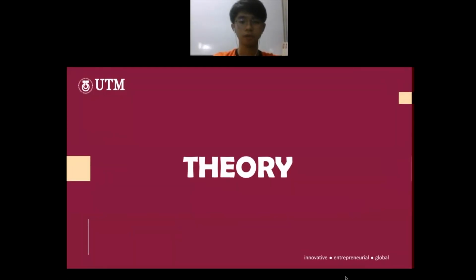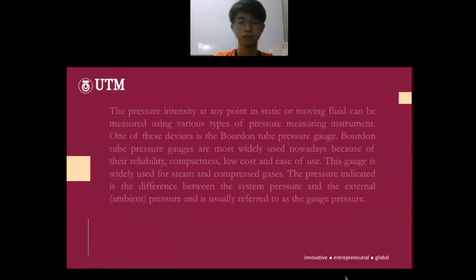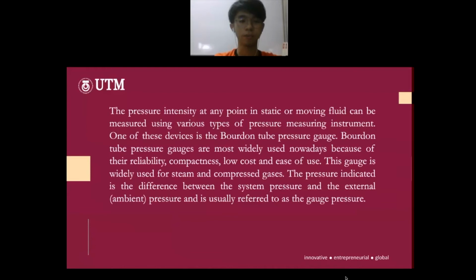So now I will continue with the theory. For this experiment, the pressure intensity at any point in static or moving fluid can be measured using various types of pressure measuring instruments. One of these devices is the Bourdon tube pressure gauge. Bourdon tube pressure gauges are most widely used nowadays because of their reliability, compactness, low cost, and ease of use. This gauge is widely used for steam and compressed gases. The pressure indicated is the difference between the system pressure and the external pressure and is usually referred to as the gauge pressure.